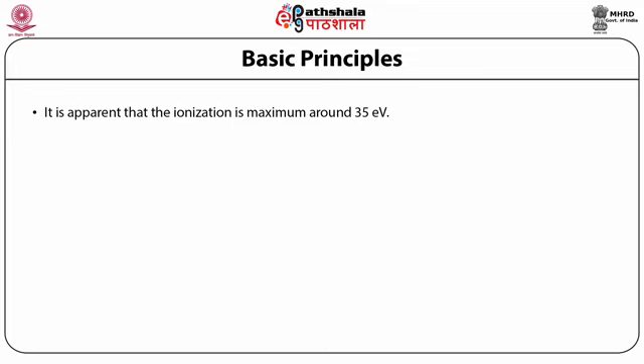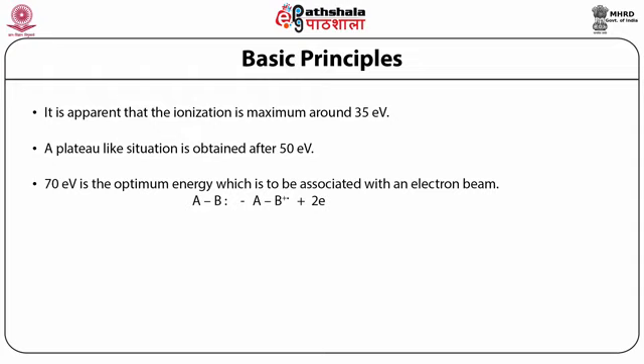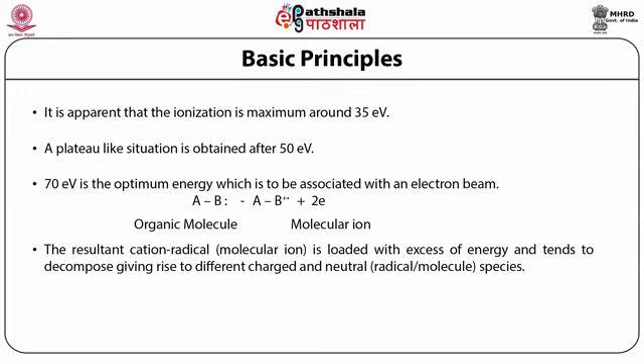Continuing with the basic principles of mass spectrometry: ionization is maximum around 35 electron volts and a plateau-like situation is obtained after 50 electron volts. Generally we give 70 electron volts, which is the optimum energy for the electron beam. If AB is an organic molecule with a pair of electrons, it is bombarded with an electron beam to give the molecular ion AB⁺• (radical cation) plus two electrons. The resultant cation radical is loaded with excess energy and tends to decompose, giving rise to different charged and neutral species, which may be radicals or molecules. The resultant charged species are called fragment ions.